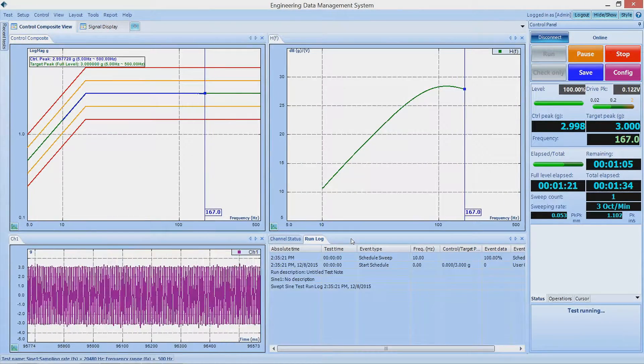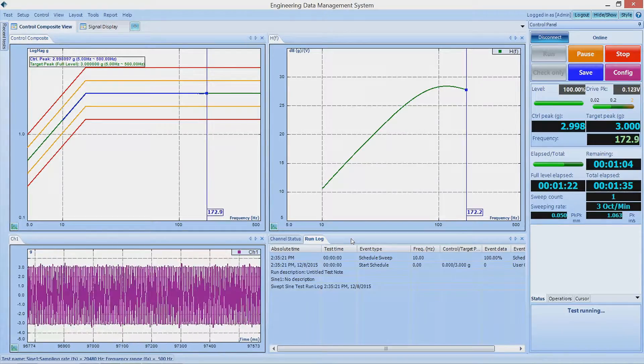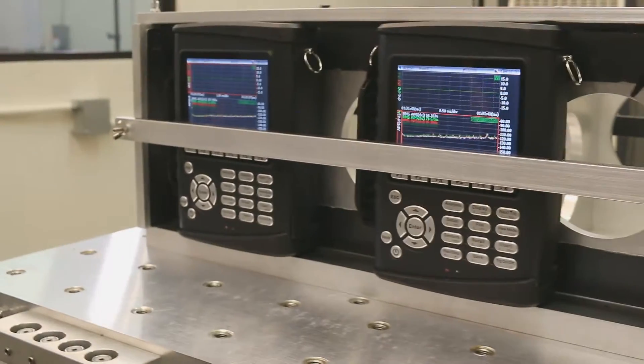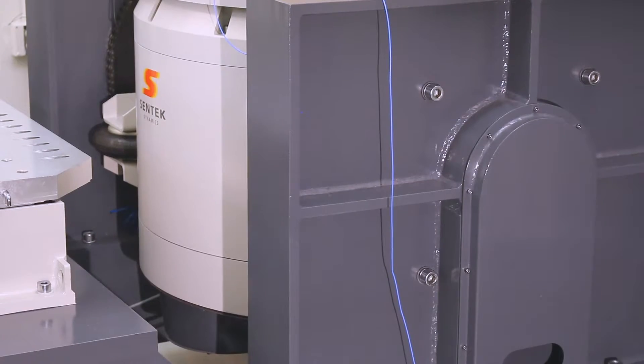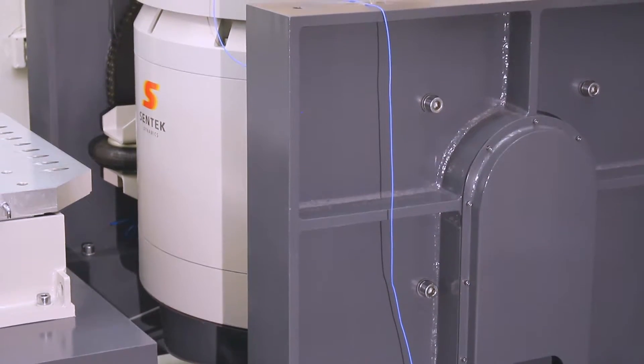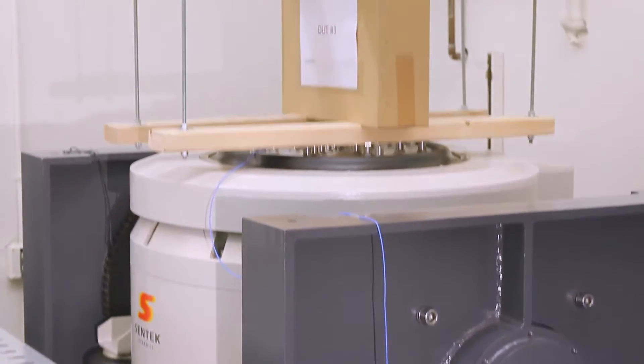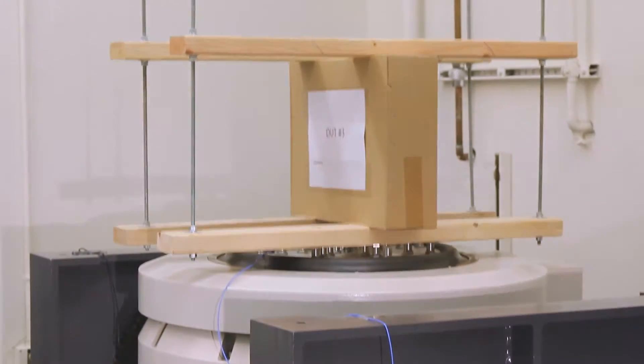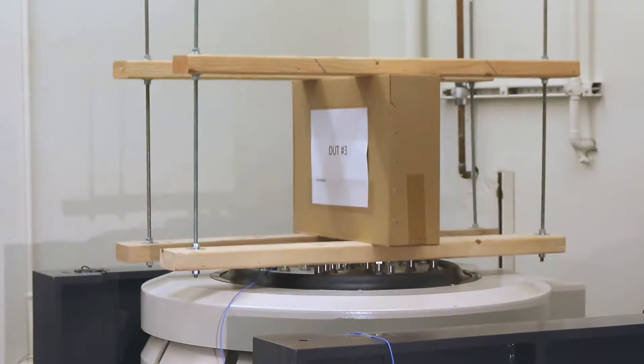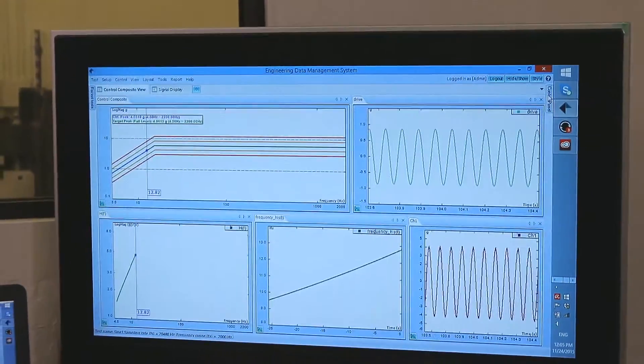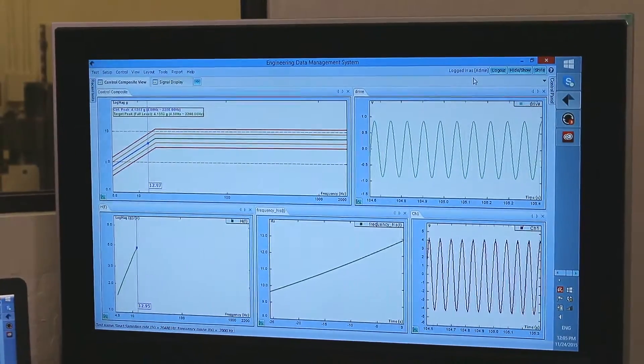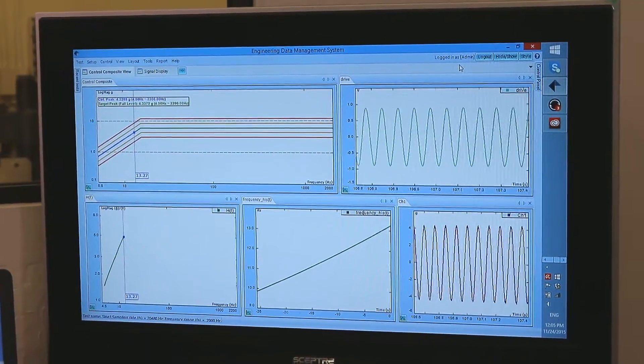The test profile is a graph of amplitude versus frequency. The swept sine control process consists of generating a sine wave output to excite the device under test. When the control signal input amplitude is detected, the detected level and the reference amplitude are compared and the drive signal amplitude is updated appropriately.